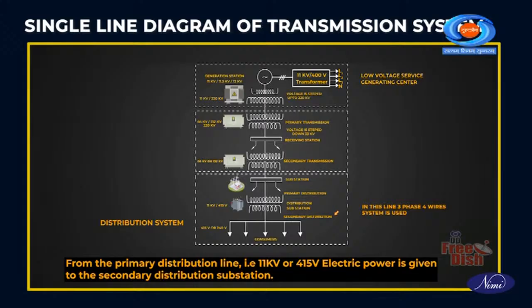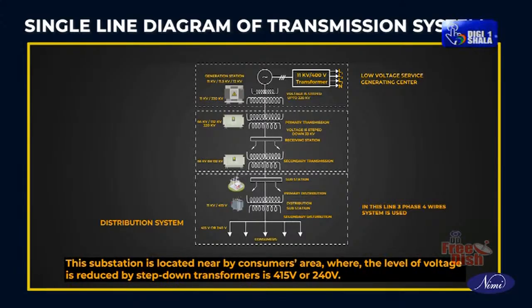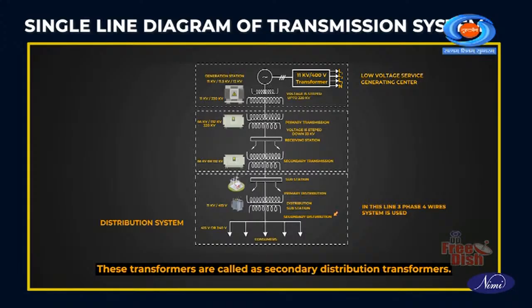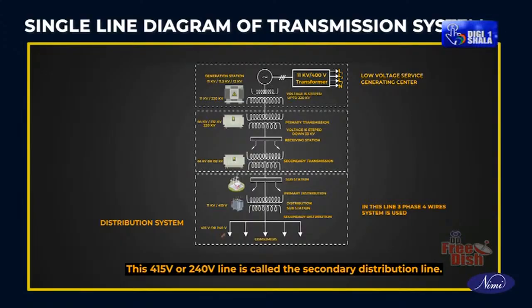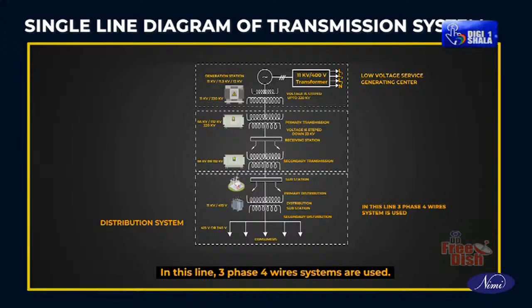secondary distribution substation. This substation is located nearby consumers area where the level of voltage is reduced by step-down transformers to 415 volts or 240 volts. These transformers are called as secondary distribution transformers. This 415 volts or 240 volts line is called the secondary distribution line. In this line, 3-phase, 4-wire systems are used.